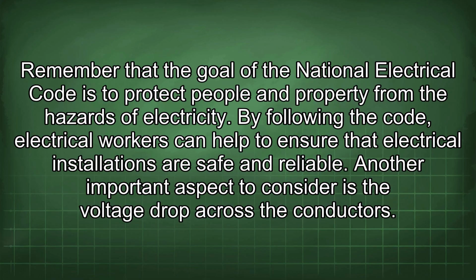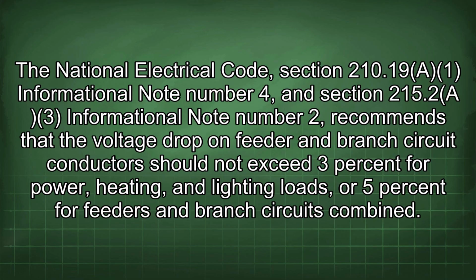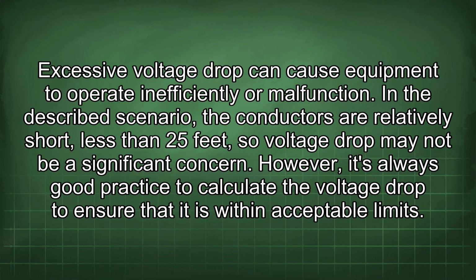Another important aspect to consider is the voltage drop across the conductors. The National Electrical Code, Section 210.19(A) Informational Note No. 4 and Section 215.2(A)(3) Informational Note No. 2 recommends that the voltage drop on feeder and branch circuit conductors should not exceed 3% for power, heating, and lighting loads, or 5% for feeders and branch circuits combined. Excessive voltage drop can cause equipment to operate inefficiently or malfunction.